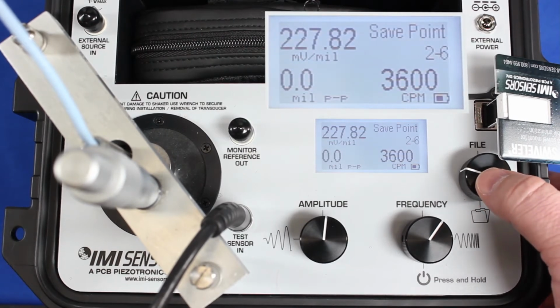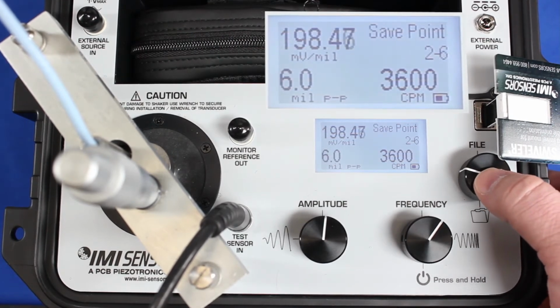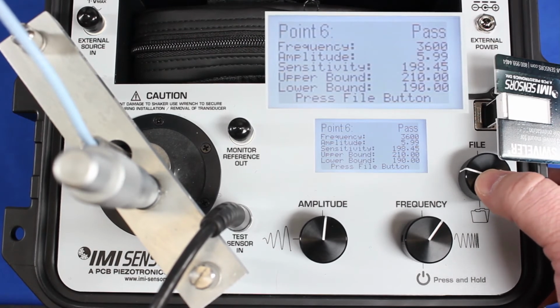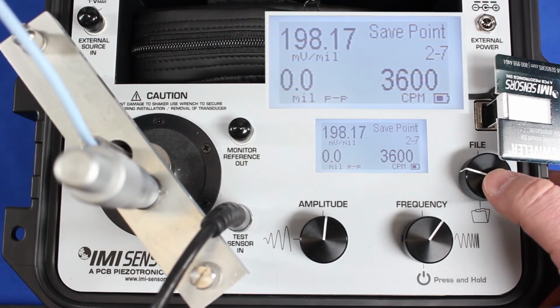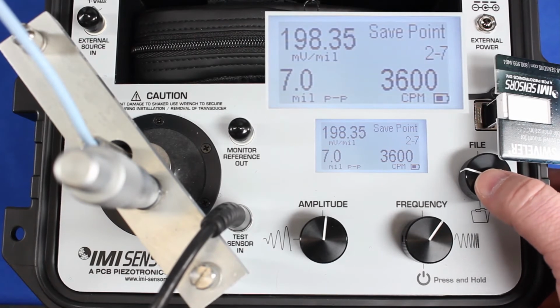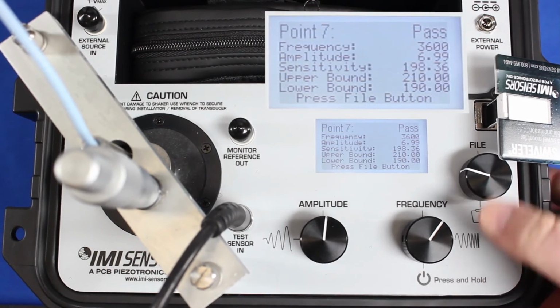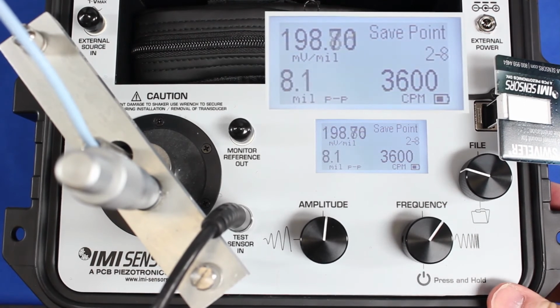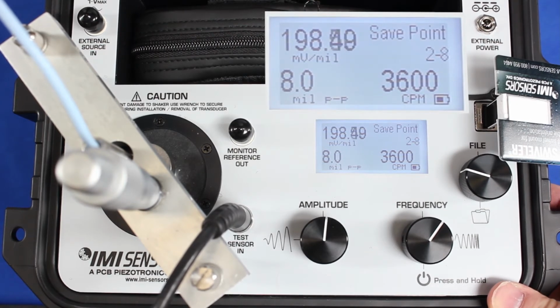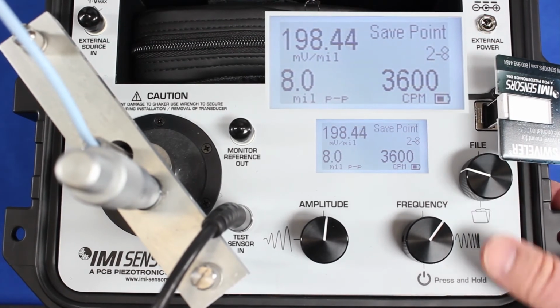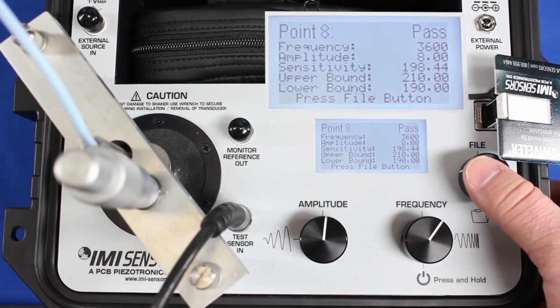I'm going to continue this test all the way to 10 mils peak to peak, stopping every 1 mil. And this test is automated. I just need to hit the file button to go from point to point. 6 mils, we pass again. 7 mils at 3600 CPM, we pass. And at 8 mils, this may be where my vibration shutdown occurs. So per API 670, I really want to make sure that the shutdown logic works in this case, the time delays work, and the turbine or compressor will actually shut down when I simulate 8 mils peak-to-peak vibration at 3600 CPM. And again, we pass at this point.